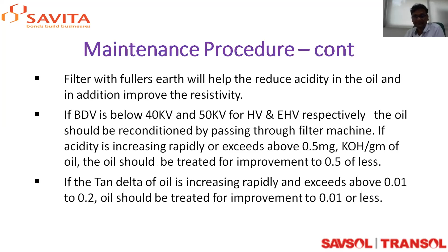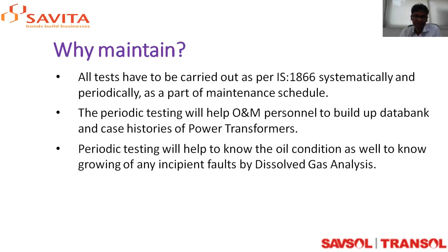So all the tests should be carried out as per IS 1866 systematically and periodically, as per the guidelines, as a part of the maintenance schedule, and strictly should be interpreted with the past values, and to have a graphical representation of how it is increasing. So periodic testing will help O&M to build a data bank and to have case studies for futuristic transformers also. When you have a few new transformers, you can use this data to make certain design changes or modify certain things. This data will always be helpful for everybody. Next slide.